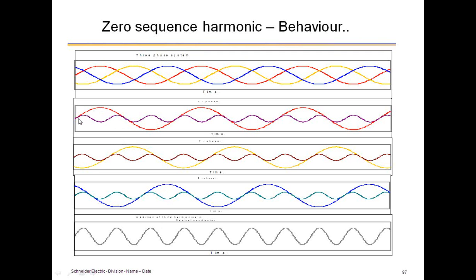The waveform just below line 1 has 3 cycles, 1, 2, and 3 cycles. It's called the third harmonic frequency. So if you compare the third harmonic component in all 3 lines, it's in the same phase. There is no phase angle difference between the third harmonic current of line 1, line 2, and line 3. So this is called zero sequence harmonics. This harmonic will add up arithmetically, and you'll get 3 times the harmonic at each phase. So the harmonic will add up in neutral, and neutral will have huge current compared to phase current.